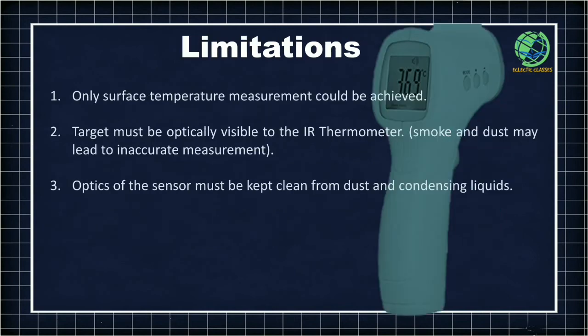As something having advantages must also have limitations, what are those limitations? Infrared thermometers can measure the temperature of surfaces only, and for measurement the target must be optically visible to the thermometer. Due to smoke or dust present between the object and the thermometer, an inaccurate measurement will result. Additionally, the optics of the infrared thermometer sensor must always be kept clean, as dust or any condensing liquid will also cause inaccurate measurement.